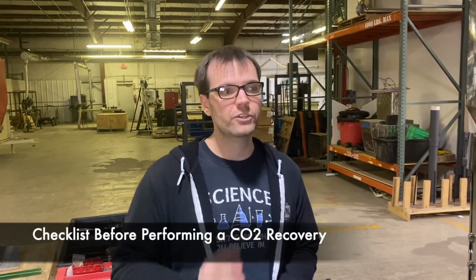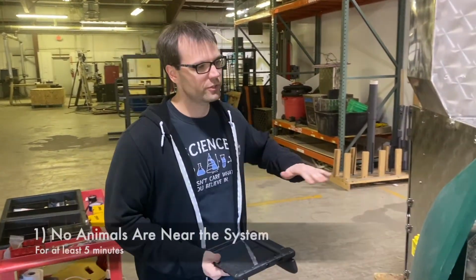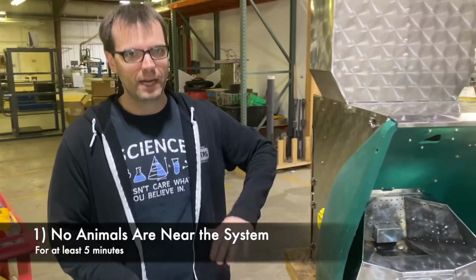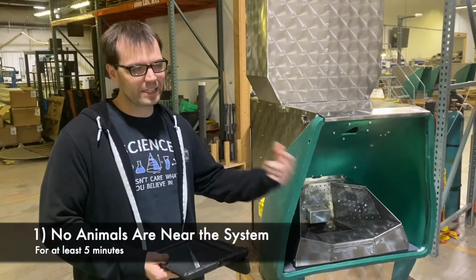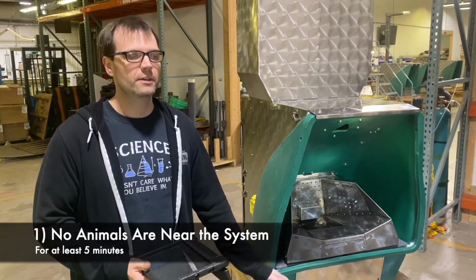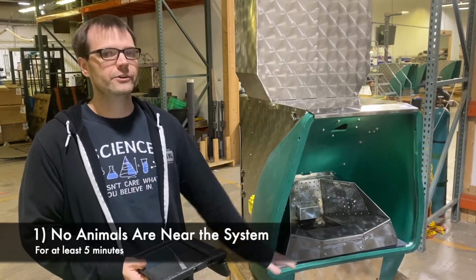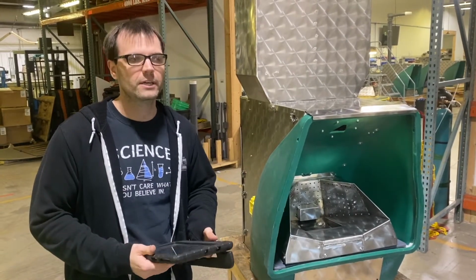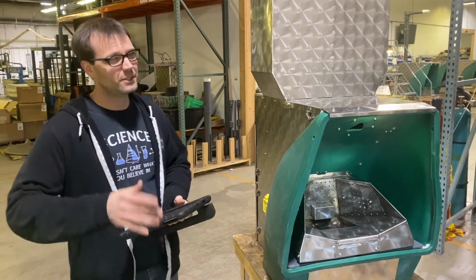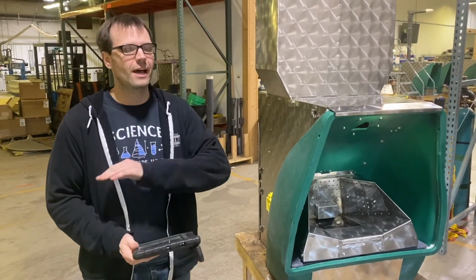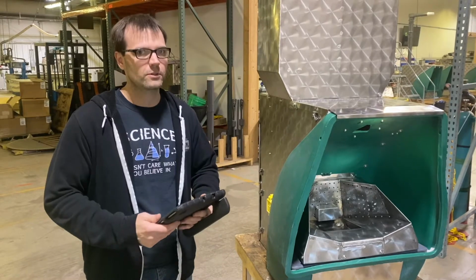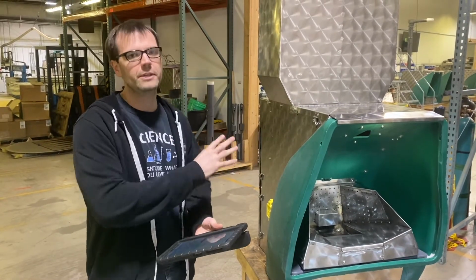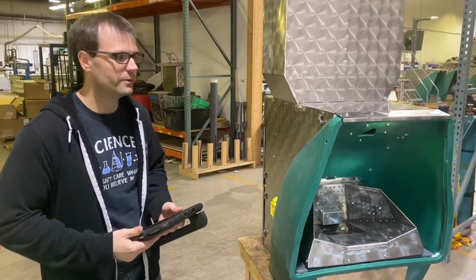All right, now we're going to show you the checklist of things that you need to make sure are correct before we start a CO2 release. The first thing, you want to make sure that no animals have been around or using the system for at least 5 minutes before you do a release. And you want to continue this the entire duration of the CO2 recovery. So the recovery usually will take about 15 to 20 minutes, so that entire duration you don't want animals or people near the system breathing into it because we release CO2.